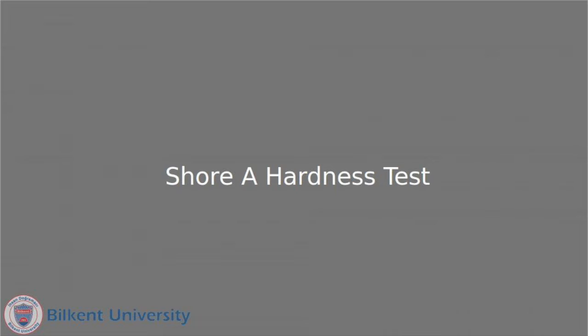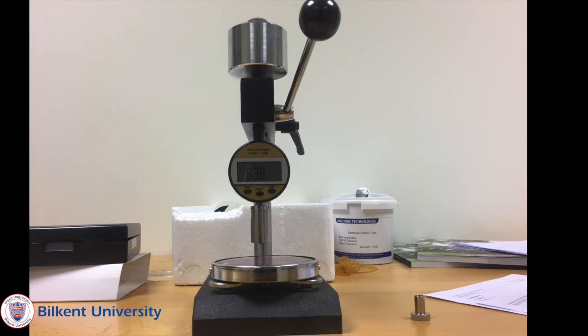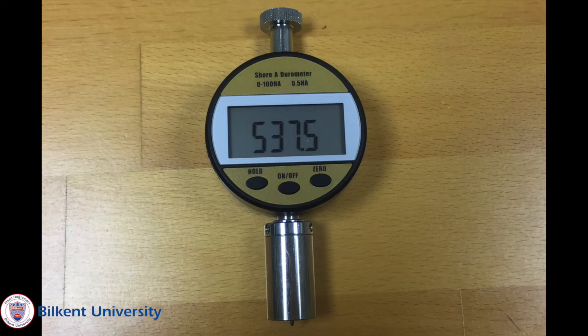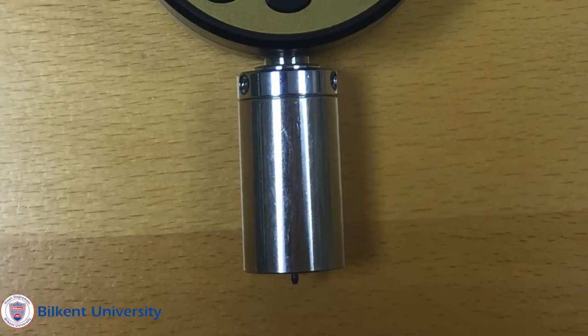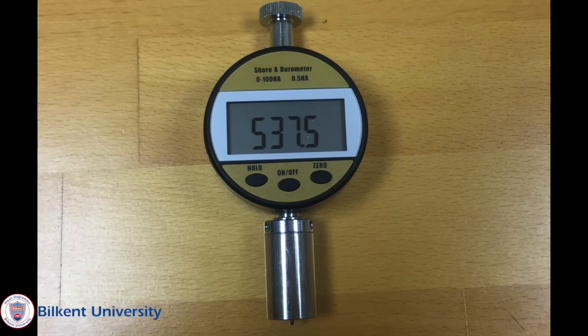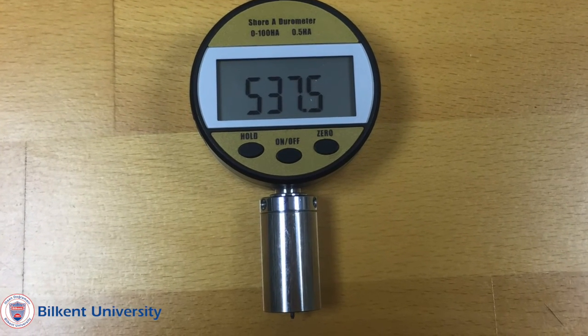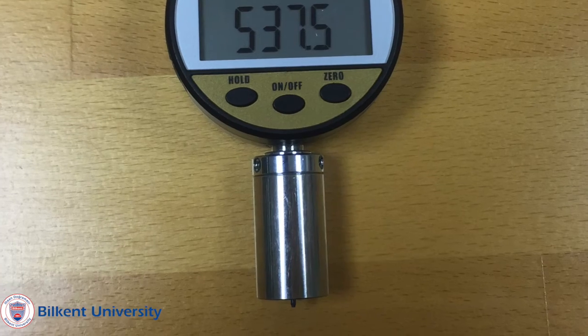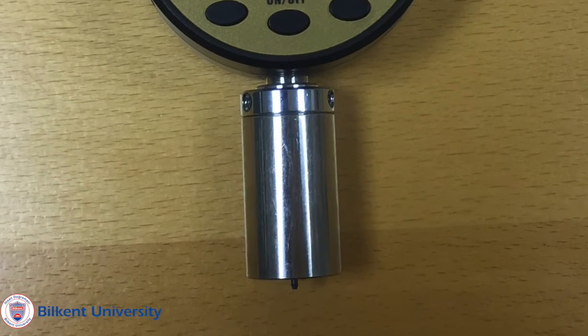The durometer displays the Shore hardness values with a value of 0 indicating no resistance to deformation and 100 indicating extreme resistance to deformation. In this experiment, our setup shall be mounted on a test stand. The test stand consists of a Shore A durometer with a display screen, a needle at the bottom, and 3 buttons. The hold button keeps the value on the display, and the 0 button is used for calibration.